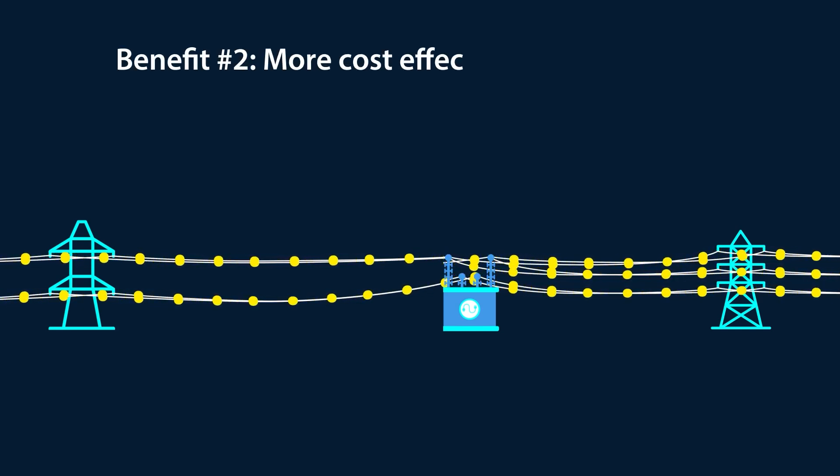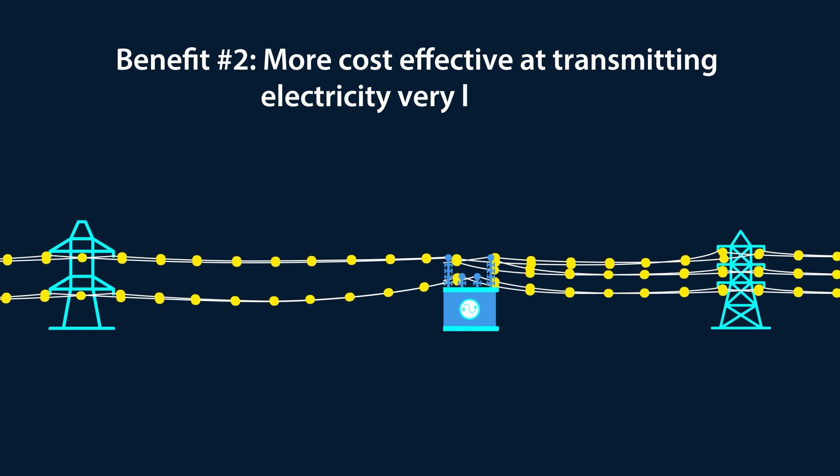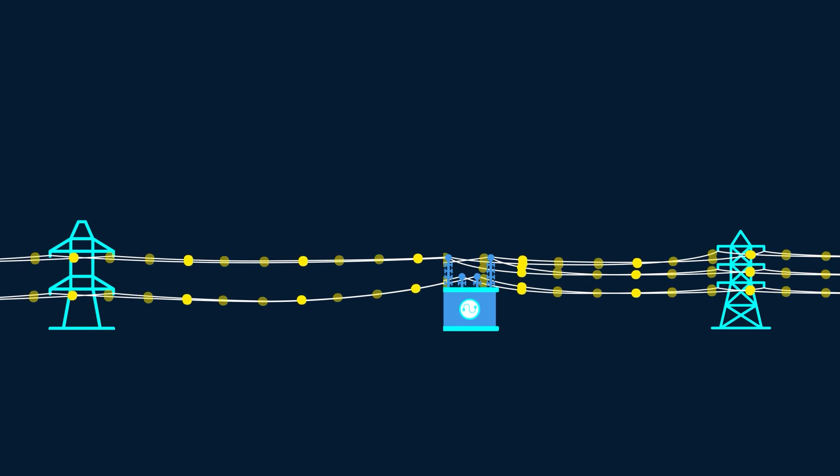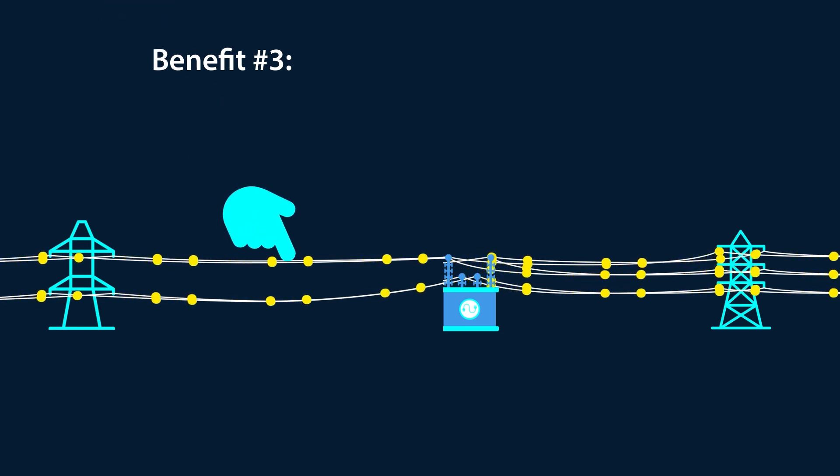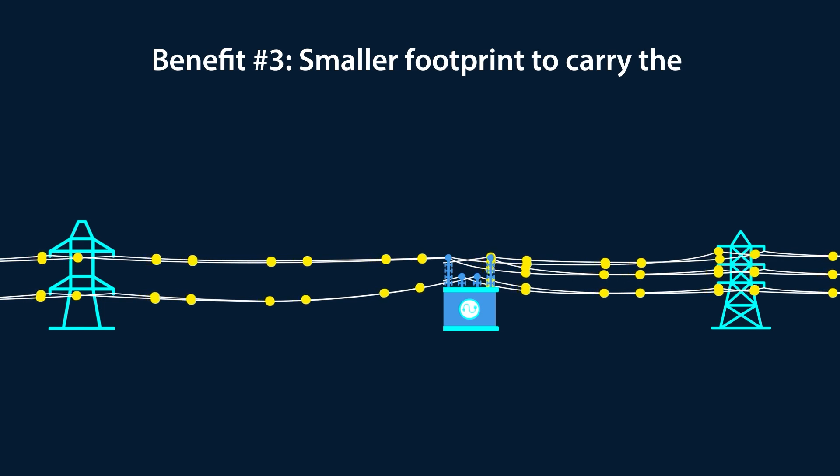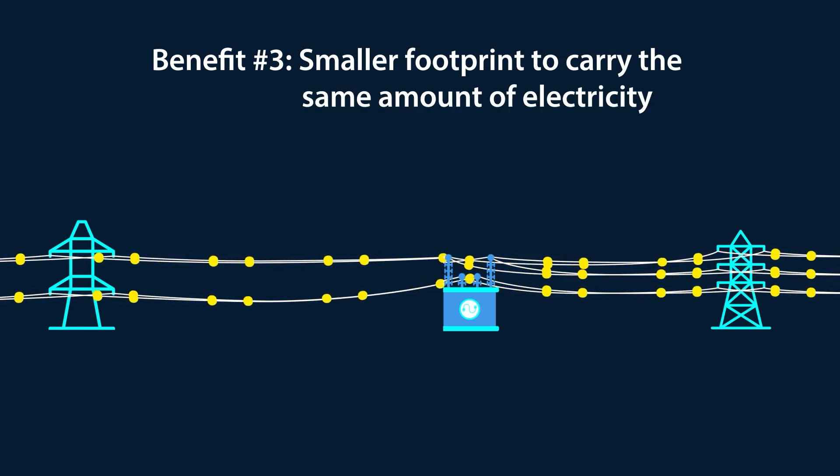Second, HVDC lines are more cost-effective at transmitting electricity very long distances. It's normal to lose some electricity when transmitting at long distances, but HVDC lines lose less compared to AC lines. Third, because an HVDC line has two wires compared to three on AC lines, it has a smaller footprint while carrying the same amount of electricity.